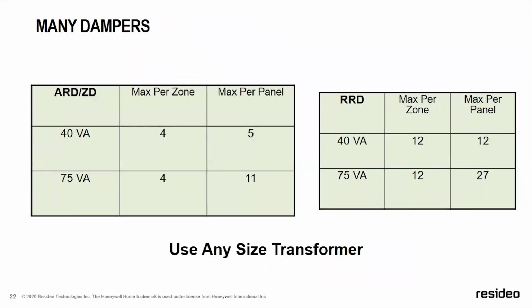How many dampers can I use? Well, the max is 4 per zone. With a 40 VA transformer, you'll notice you can use 5 per panel. If you up the VA, the volt-amps, you can use 11.